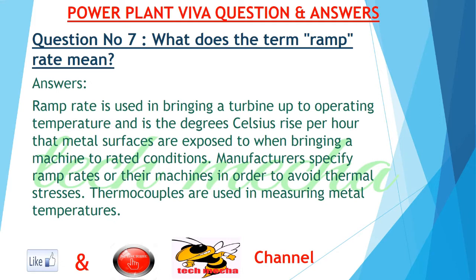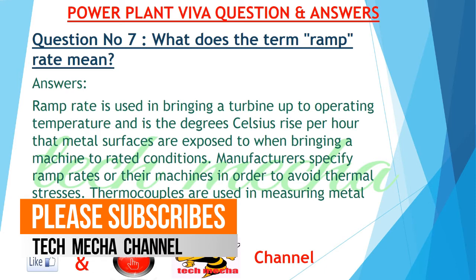Question number 7: What does the term ramp rate mean? Answer: Ramp rate is used in bringing a turbine up to operating temperature, and is the degrees Celsius rise per hour that metal surfaces are exposed to when bringing a machine to rated conditions. Manufacturers specify ramp rates for their machines in order to avoid thermal stresses. Thermocouples are used in measuring metal temperatures.